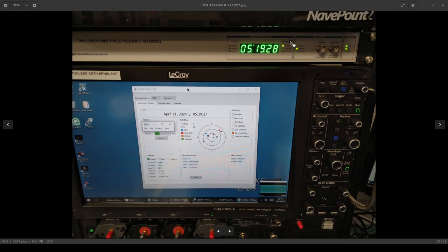And then on the right side of the display we've got a button that you can push to select whether you're displaying the current time, delta in time between PPS and UTC, or number of satellites, SNR, latitude, longitude, there's a few other parameters you can show.